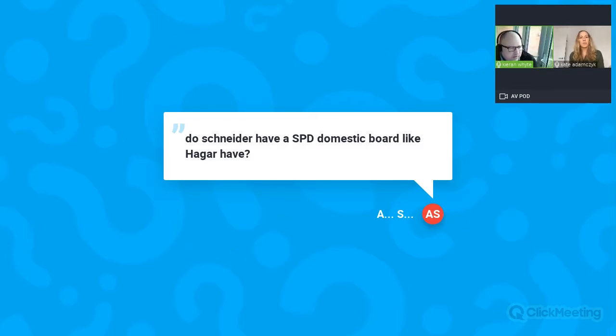We have 2 variants, a 6 and a 7-way split load comes with the SPD, and we have a 3, 5 and 5 high integrity way. We also offer the SPD on its own as a kit, and that comes with the additional cables then to connect it to the phase and the neutral bar and the earth bar.